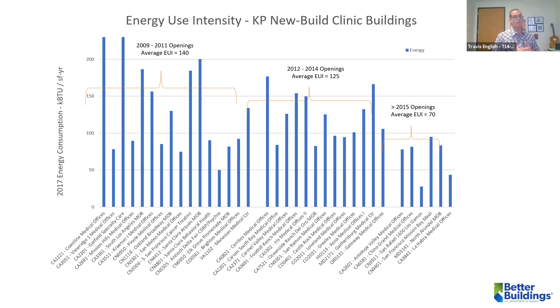That takes us back to this Santa Rosa medical office building. Since I told you we're a net zero building, let me give you the bad news: when we say zero, we mean 5. I'm told once a building gets below 10 EUI, you can claim it as net zero, so we're going by that rule. First patient was May 2018. We started the measurement and verification period in September, so we have a full year - the 5 EUI is a September to September number. This building consumed 36.8 EUI, and in the same period on-site solar production was 31.8, so net consumption was 5. We call that net zero.